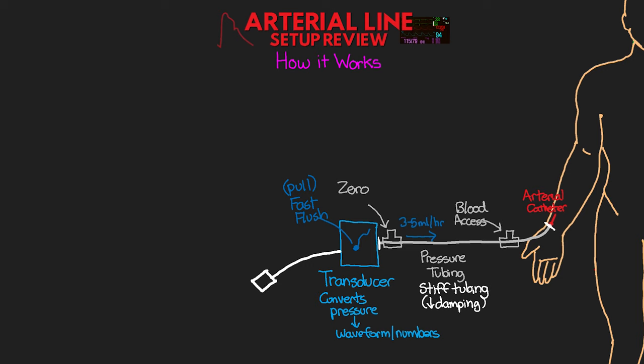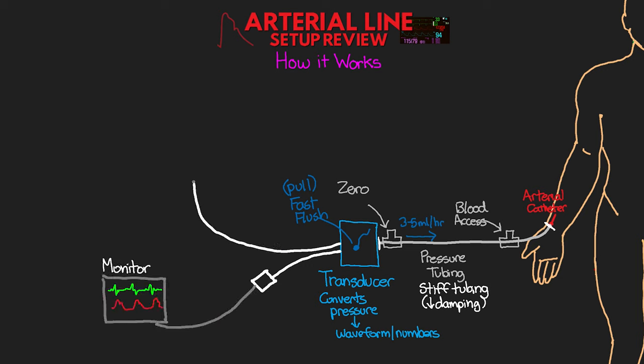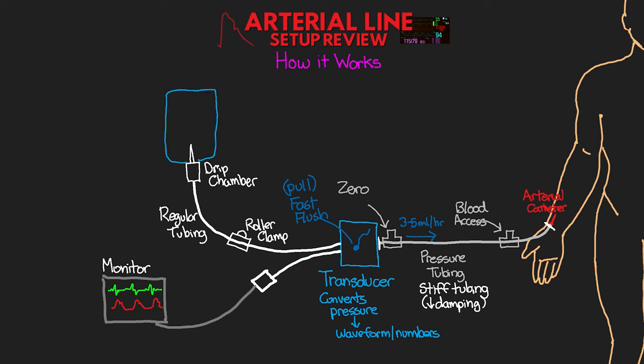First is going to be the connector to attach the cable that's going to go to our monitor. And then next will be regular tubing that has a roller clamp and goes to a drip chamber with a spike at the end. The spike here is used to spike your bag of saline. The saline bag will be inside of the pressure bag that I mentioned, and it is important that this does remain properly pressurized to keep the flow of saline moving forward and to ensure accuracy of the reading that we get. And so this is the overall basic setup of what we need and how this system functions at a basic level.